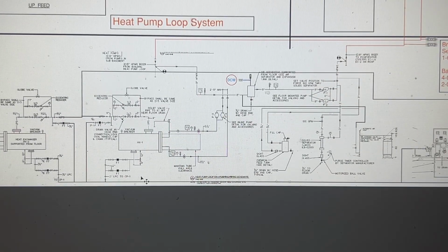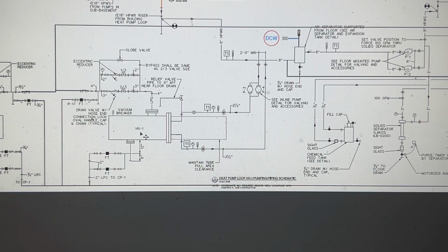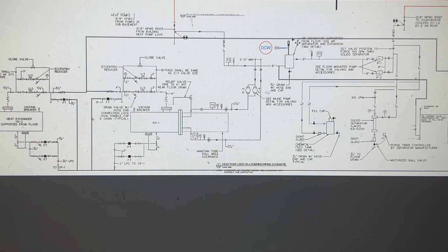Okay. So we talked about before, the cooling tower serves as the cooling means for the heat pump loop water. Down in the sub-basement here, the heat exchanger acts as the heating element. So when we're winterized up top, when we're in heating season, we need that water to get heated up. So we've got the steam supply to this heat exchanger. We got a 1/3, 2/3 control valve system. So that will heat this bundle that has our supply and return on the heat pump loop. So that will act as the heat element for the building in the wintertime.